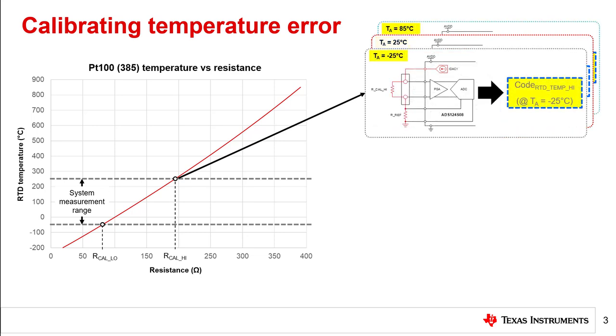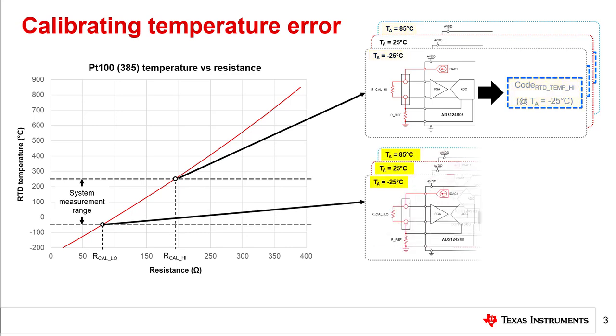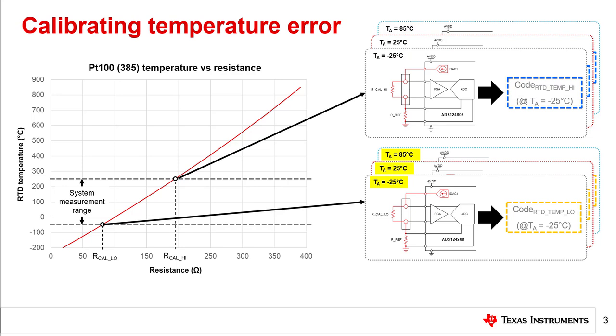Then, expose the measurement system to the desired calibration temperatures using a controlled chamber or bath. Example parameters introduced in the previous presentation used a temperature range of negative 25 degrees Celsius to 85 degrees Celsius, so we will also calibrate at these two temperatures. However, more calibration points can be used, which improves the overall calibration results and can be useful for a non-linear temperature response. The images in the top right show these additional two measurement points and resulting ADC output codes for RCAL high. The images on the bottom right show how the process is repeated and the same three measurements are taken for RCAL low.